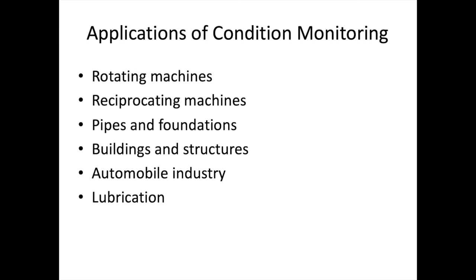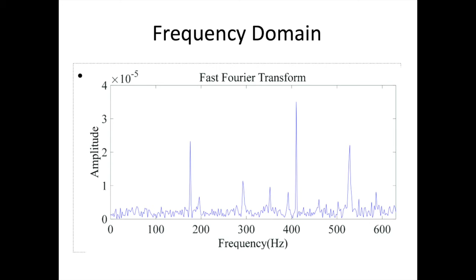Like how a doctor takes a cardiogram and sees the condition of a patient's heart, in a similar way the frequency domain, or frequency spectrum, or fast Fourier transform, what we call FFT, which is very popular, can tell you the exact problem with the machine when there is high vibration. So with the help of the FFT spectrum, or cardiogram of the machine, we can pinpoint whether it is misalignment, unbalance, looseness, or damage. And there are so many other condition monitoring problems, and these are checked by a vibration sensor called an accelerometer.